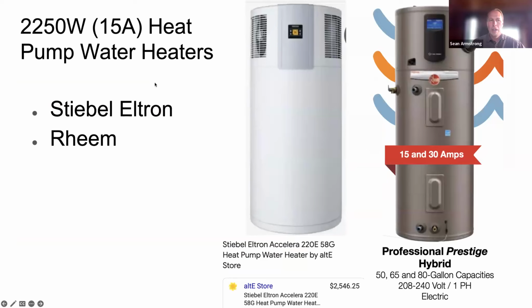There are two kinds of heat pump water heaters, with a range of power they take. Some of them take 30 amps, which equates to 4,500 watts—like 2.5 hair dryers on full blast. You can also get 15 amp models. Stiebel Eltron and Rheem both make 15 amp, 2,250 watt units—those are the same thing. Then you can get water heaters that are like 1,400 watts, and 900 to 500 watts. But the 15 amp option is the happy medium where you have a really good heat pump doing most of the work, but also an electric resistance backup element in case it gets really cold where this is located.